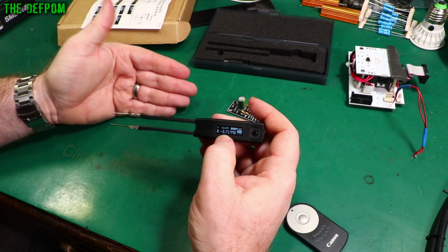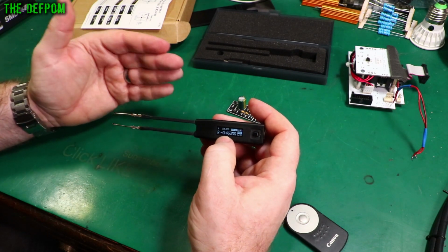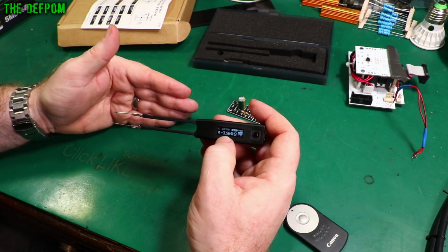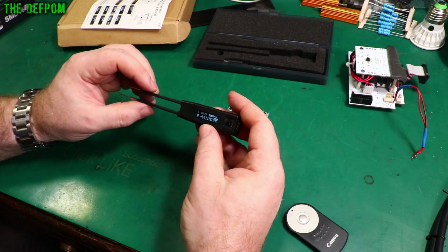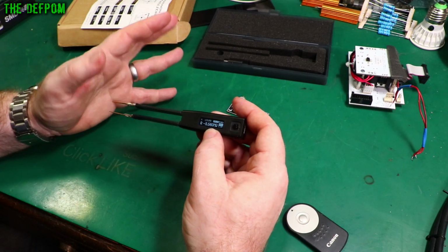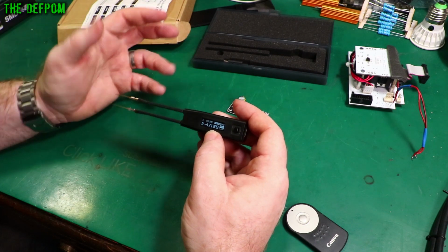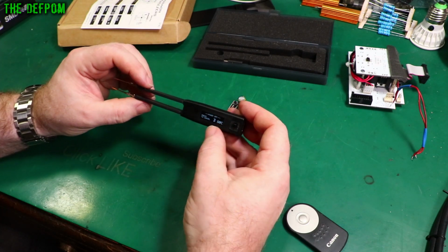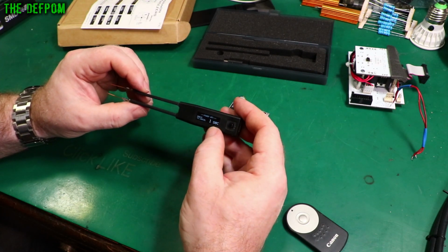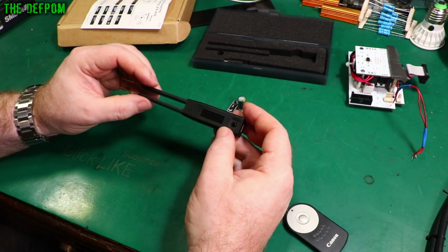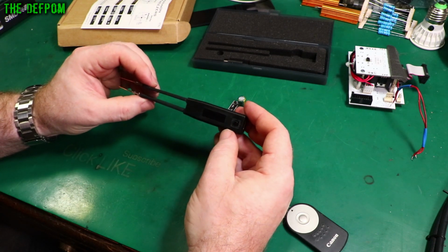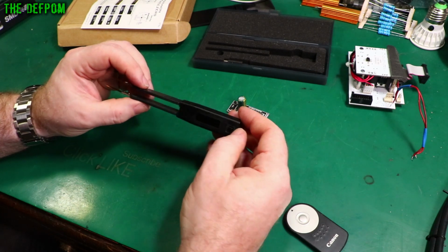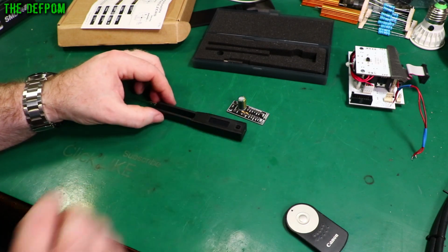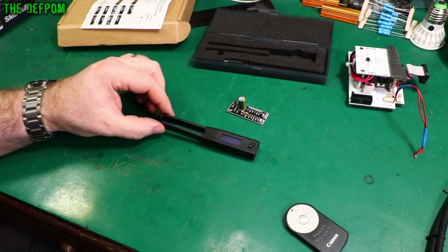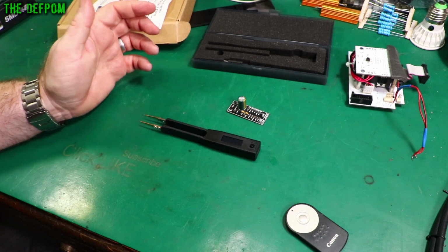So it did up to basically 100k. Okay, 100k was slightly off, but it's like 200 ohms off at 100k, and 1 mega ohm, it couldn't really read it. I think it's just too much electrical noise around here is affecting the readings too much. It was trying, and I did the DC resistance mode. It's slightly better, but it still struggled. I couldn't really read 1 mega ohm. I think it just couldn't really generate the current. So I think that's part of that problem there. So doing high resistance measurement on it is probably a bit tricky unless you're in a particularly quiet environment.